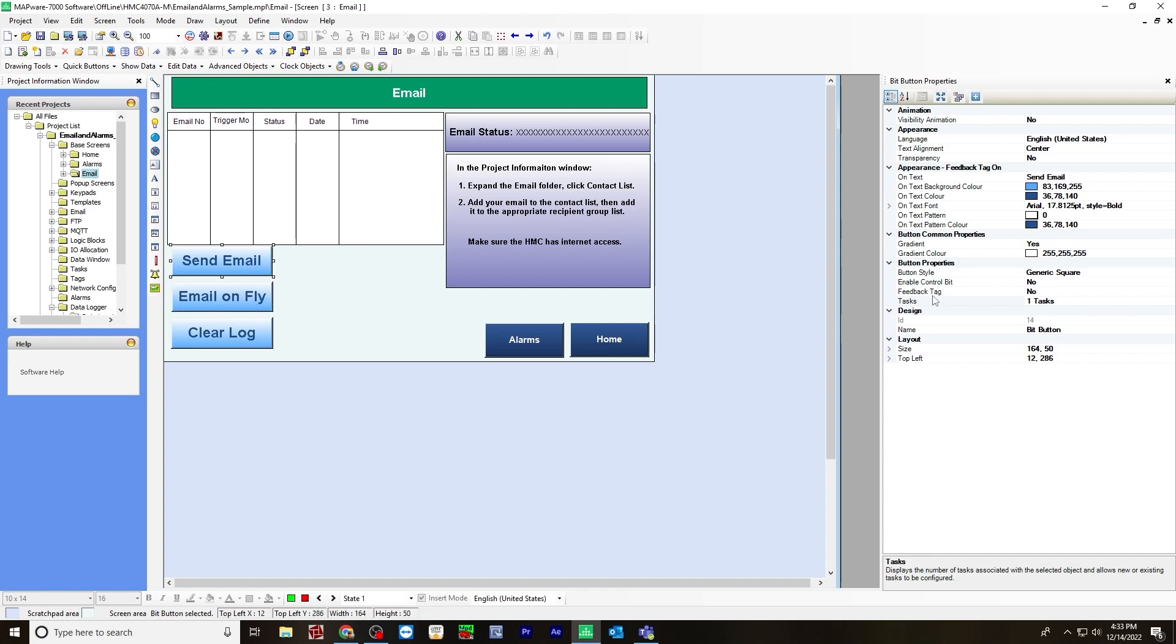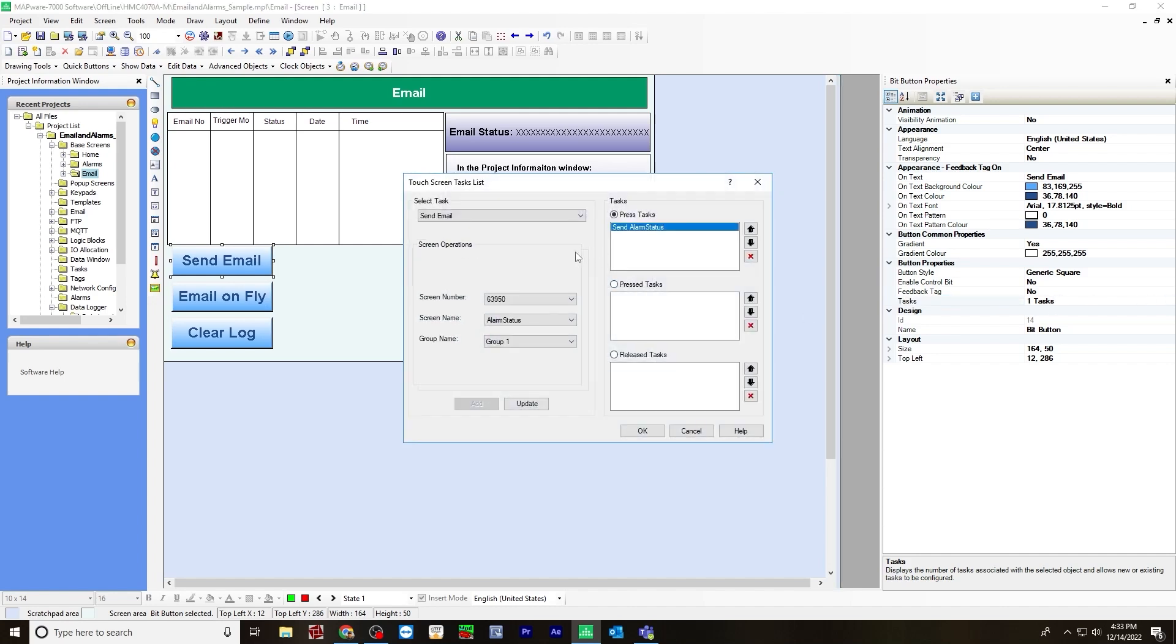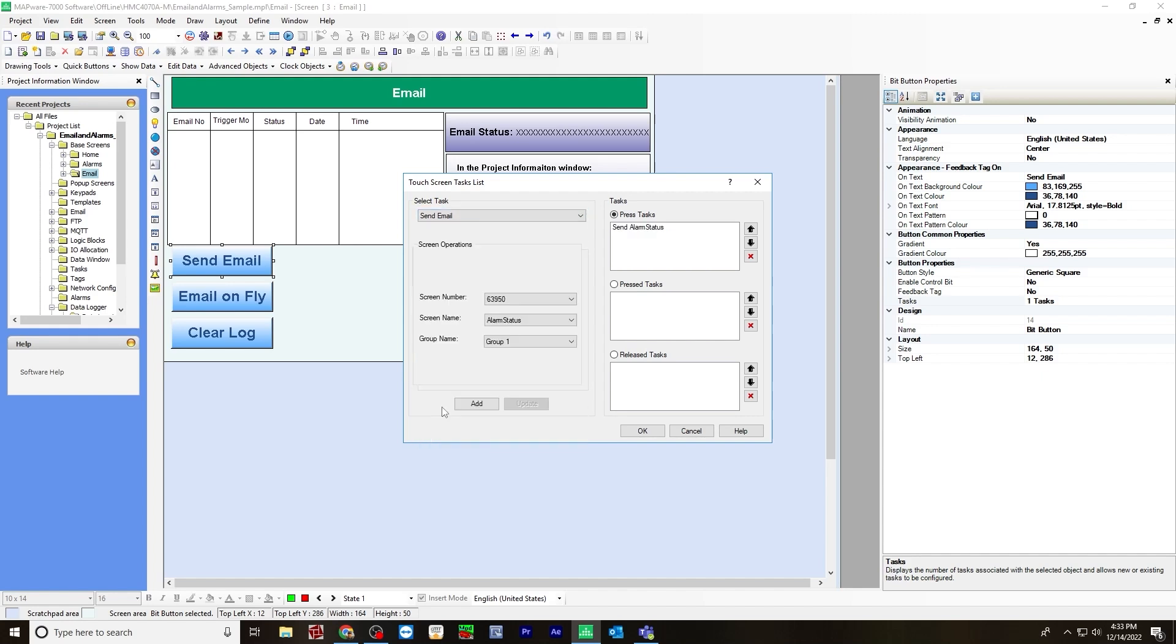So for sent email, the task will be send alarm status. So for the task, you go to send email. For screen number, this will be the screen number. And the screen name will be the name of the email. The screen we created, alarm status, and then group one, which is the only group we have. Hit add, and it will go over to the press task. And then hit OK.